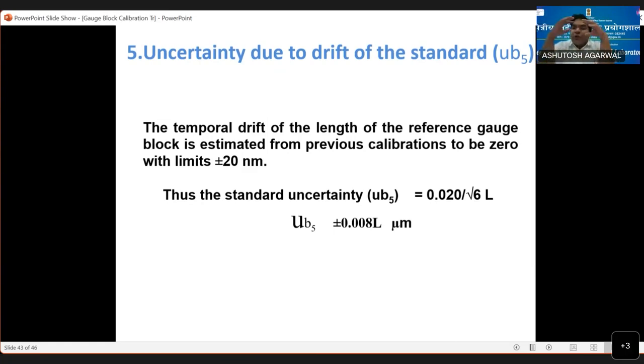So what happened? Our steel is made of ferrous iron. So generally after 1 to 10 years, iron and carbon get precipitated. The same happens in tungsten carbide also. That will get precipitated over time. When it gets precipitated, it gets shrinkage, mostly shrinkage. So that is the drift in the standard when you use it regularly for 10 years. That is because of shrinkage, because of their internal bonding.